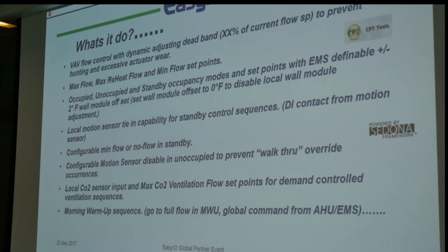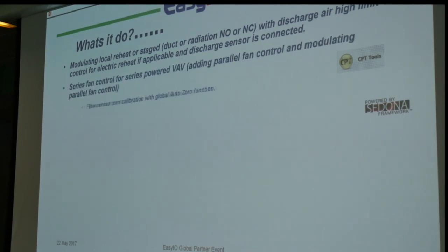You've got CO2, you've got the ability to take a local occupancy sensor, you've got obviously your CFM flow set points in there, morning warm-up sequences, everything. A VAV is a VAV is a VAV. You've got modulating, reheat, staged, normally open, normally closed, radiation, discharge high limit if you have electric heat. Series fan control is typical, and we're also adding parallel fan control and then modulating parallel fan control.